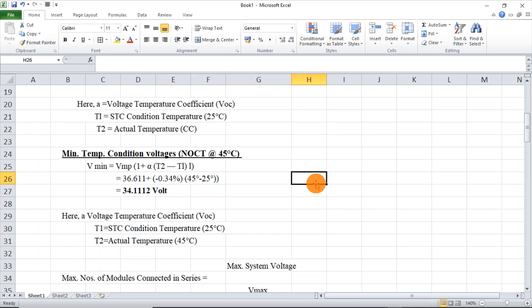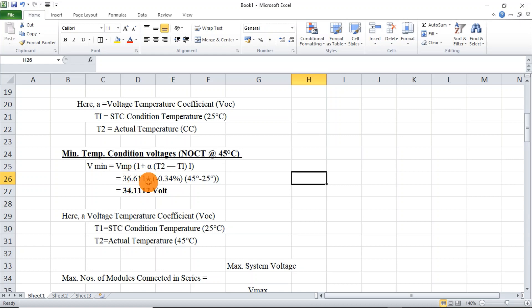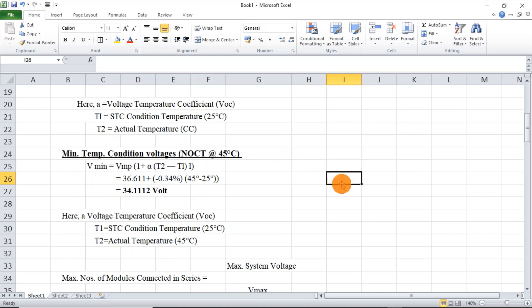For the minimum number of modules to be connected in series, the formula is: Vmin = VMP × (1 + α × (T2 − T1)). VMP is the maximum power voltage from the module. Alpha remains the same. T1 is the standard test condition temperature, 25°C. T2 here is taken as 45°C, which is the maximum actual temperature inside the installation. Solving this, we get a voltage of 34.1V.